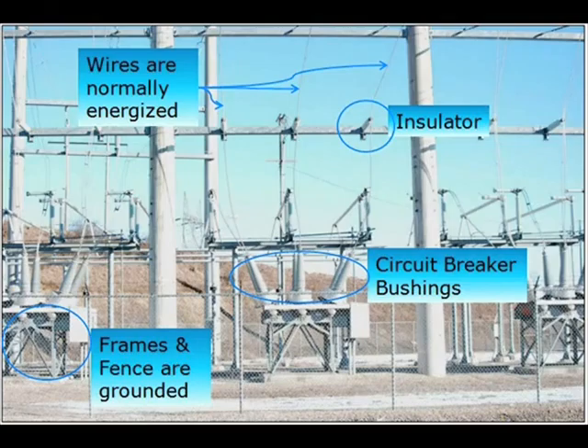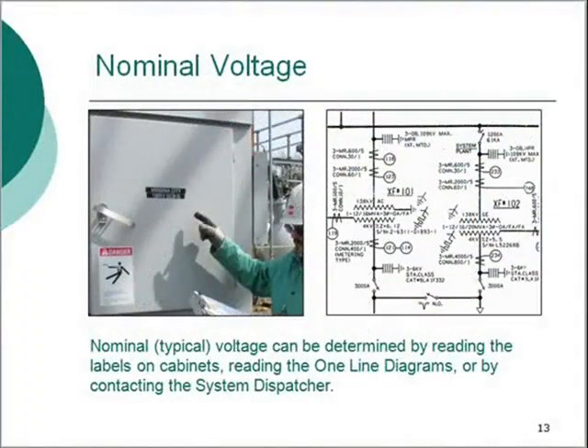By looking closely and following the path of each wire, you can see that the insulators maintain a safe distance between energized lines and support structures. In addition, the supporting structures and metal framework are grounded. Nominal or typical voltage can be determined by reading company labels on cabinets and operating mechanisms, reading the substation one-line diagrams, or by contacting the system dispatcher.